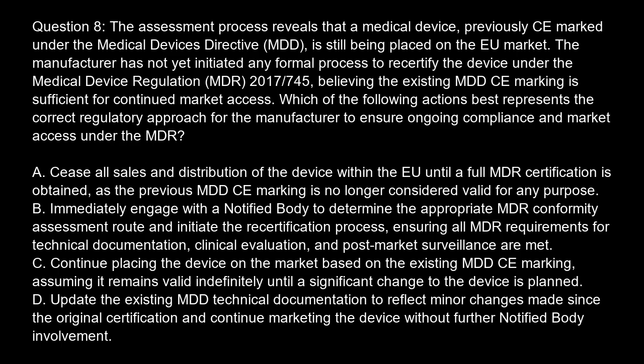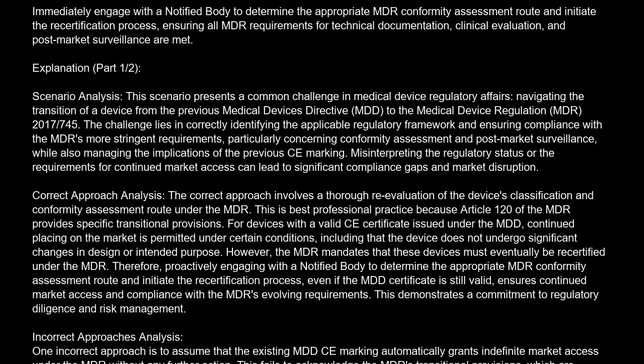Option C. Continue placing the device on the market based on the existing MDD CE marking, assuming it remains valid indefinitely until a significant change to the device is planned. Option D. Update the existing MDD technical documentation to reflect minor changes made since the original certification and continue marketing the device without further notified body involvement. The correct answer is B. Immediately engage with a notified body to determine the appropriate MDR conformity assessment route and initiate the recertification process, ensuring all MDR requirements for technical documentation, clinical evaluation, and post-market surveillance are met.